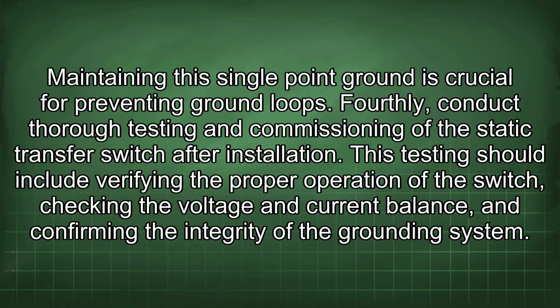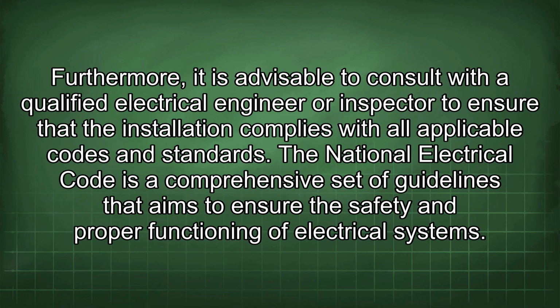Fourthly, conduct thorough testing and commissioning of the static transfer switch after installation. This testing should include verifying the proper operation of the switch, checking the voltage and current balance, and confirming the integrity of the grounding system. Furthermore, it is advisable to consult with a qualified electrical engineer or inspector to ensure that the installation complies with all applicable codes and standards.